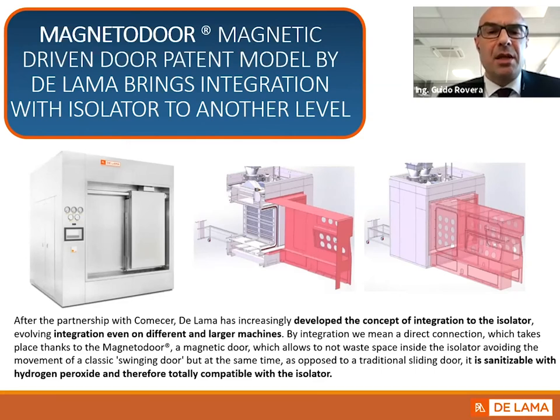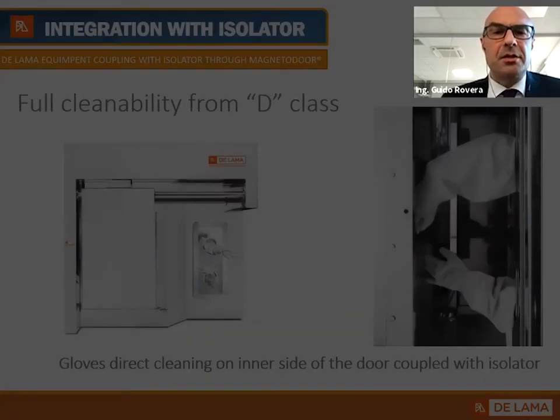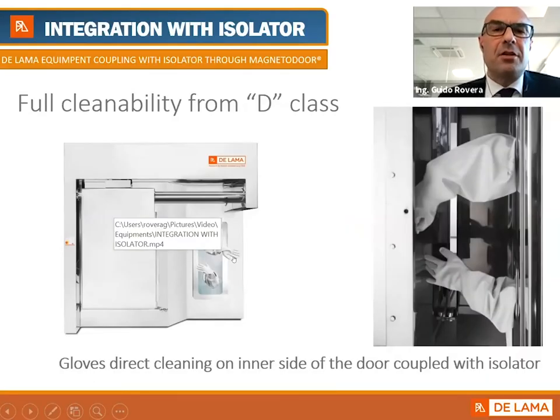At the same time, the magnetic driven door allows sanitization by hydrogen peroxide, as normally occurs inside the isolators. Another interesting part of the magnetic door is that once integrated in an isolator, the rear part of the doors can be reached by gloves and therefore also manually cleaned in case of need.